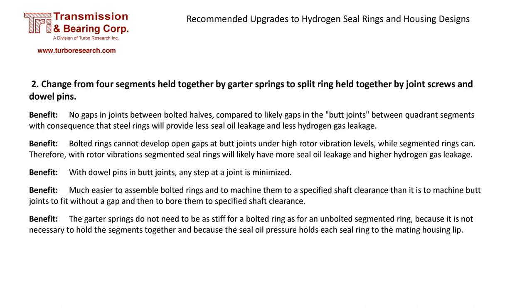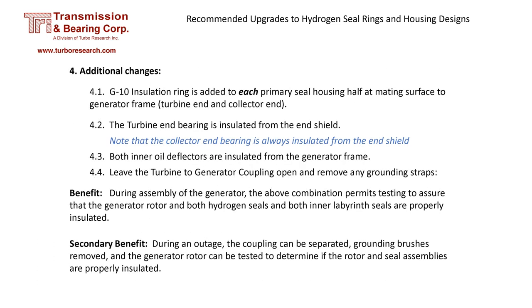Bolted rings have no gaps that can open up during periods of high vibration, and they also have the advantage of being easier to bore to tight tolerance and assemble. Because the upgraded housing has a top with a removable section, verifying the assembly is possible. A megger test between the seal housing and frame can be performed before the rings are installed. There are benefits to insulating all the seal housings, inner labyrinth deflectors, and bearings. During an outage, the coupling can be separated and grounding brushes removed, and proper electrical isolation can be tested without having to remove the seal housing or labyrinth seals.